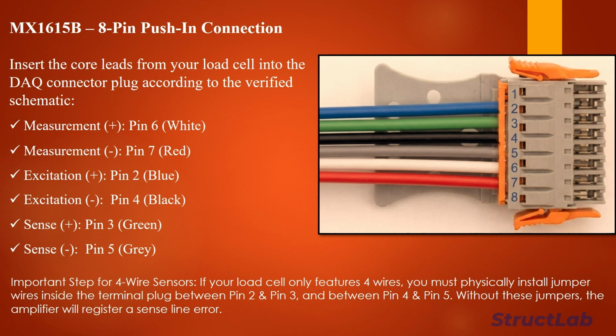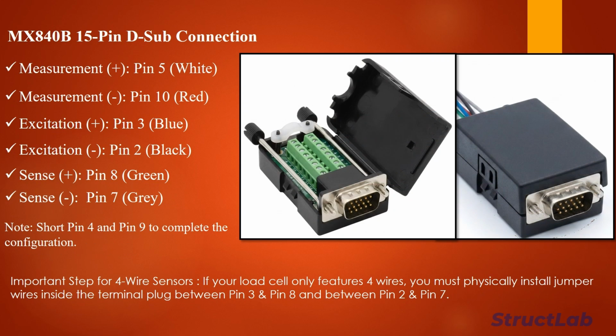If you are using the MX 1615B module, insert the core leads directly into its 8-pin push-in connector as shown here. White goes to pin 6, red to pin 7, blue to pin 2, black to pin 4, green to pin 3, and gray to pin 5. Please note that if you are using a 4-wire sensor instead of a 6-wire version, you must physically install small jumper wires inside the plug between pins 2 and 3, and pins 4 and 5 to prevent a sense line error.